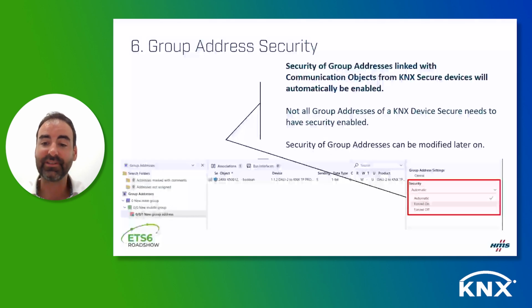Here we will decide how to apply this security for the group address or communication object: force on, force off, non-security, or automatic if ETS detects that there are two devices that are secure. Of course, if I set forced on and try to link this group address with a communication object that is not secure, I will receive an error message from ETS saying it cannot be done.